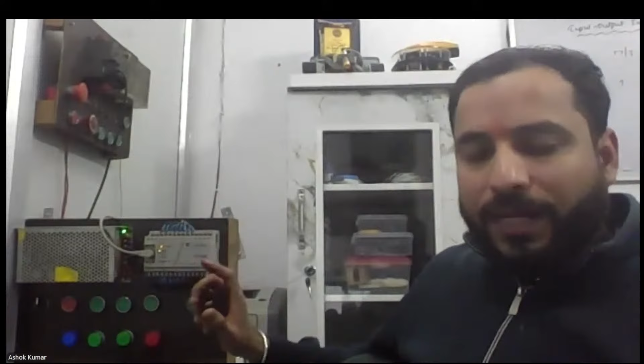When we're talking about the hardware, look at this. We have six inputs and four outputs, correct? So obviously, whenever we work with the hardware, the PLC needs input from your side about which input button or which input sensor you are using, because we have six. So you need to mention in your program whether you are using the first one, the third one, or the last one. For that, we need addressing methods. So now we need to understand the addressing methods. That is called data files. These addressing methods may differ from PLC to PLC. Currently I'm telling you according to Allen-Bradley. Later, once we do Siemens, obviously we need to change everything according to that.